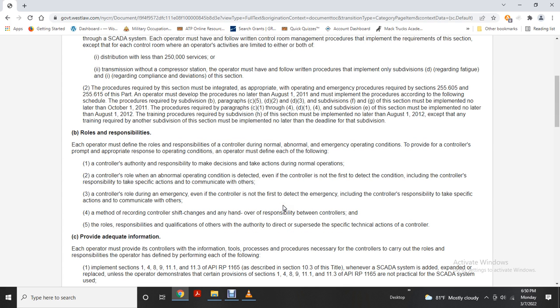Each operator must define the roles and responsibilities of a controller during normal, abnormal, and emergency operating conditions. The controller must promptly respond appropriately to operating conditions. Operator must define each of the following. The controller's authority and responsibility to make decisions and take action during normal operation. The controller's role during abnormal operating conditions, to detect the event if the controller has not first detected the condition, and include the controller's responsibility to take specific action and communicate with others.